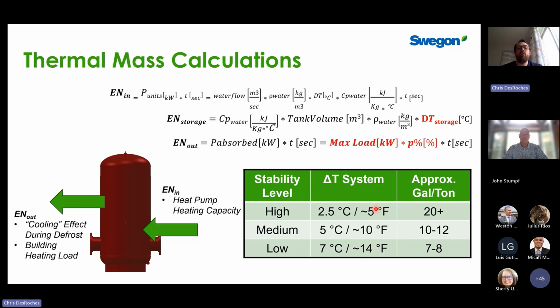Generally speaking, the more water volume you have, the less impact you're going to have on temperature. But as consultants, you're trying to find a balance between space, weight, and costs, and trying to keep the architects happy in terms of space. So rule of thumb, low stability is good for most comfort applications anyway. You're in the range of 7 to 8 gallons per ton. Medium stability would be more in the 10 to 12 range. And as you can see here, high stability is 20 plus gallons per ton. It's just way too much water.